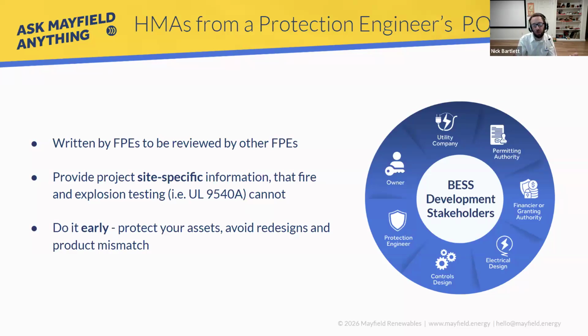Sometimes people do layers of protection analysis, so are there multiple failures stemming from a single failure? We'll look at if the battery management system fails, what might happen, and if the explosion control systems fail, what might happen. These are all described in NFPA 855 as things you're supposed to look at. You go failure by failure and assess what can prevent that failure from happening, and what you have in place to mitigate any consequences if that particular system fails.